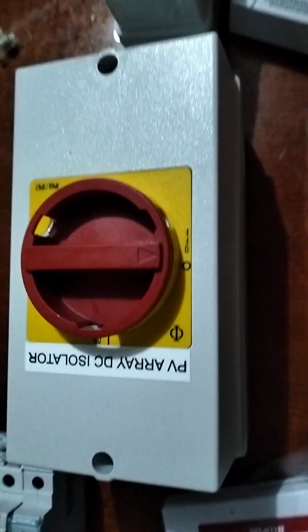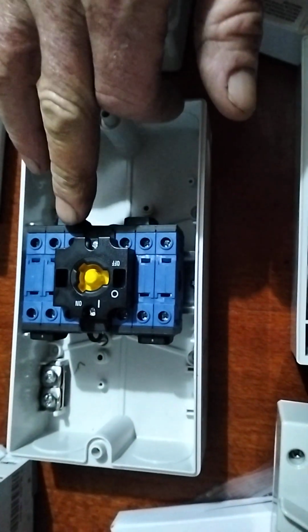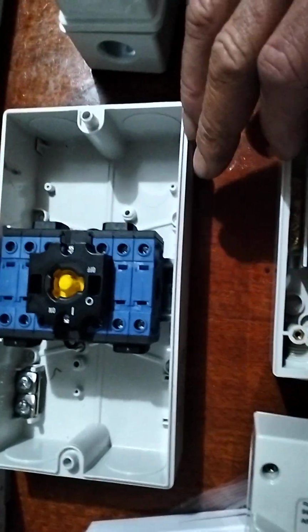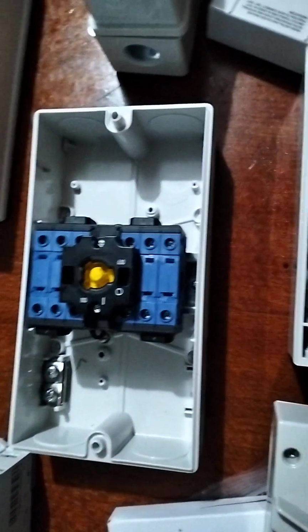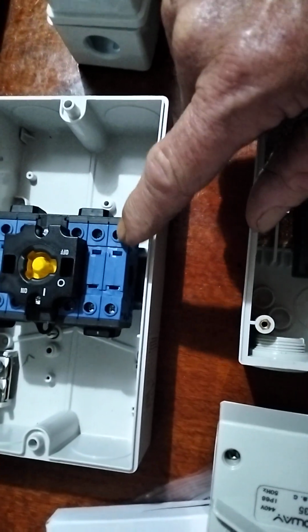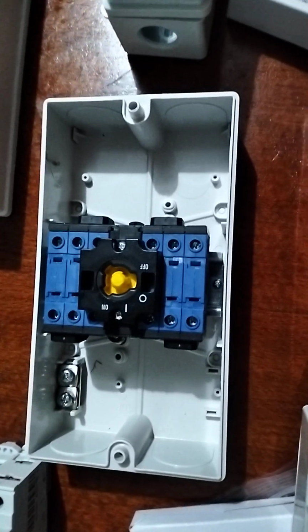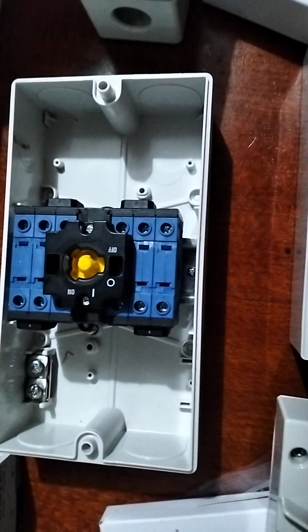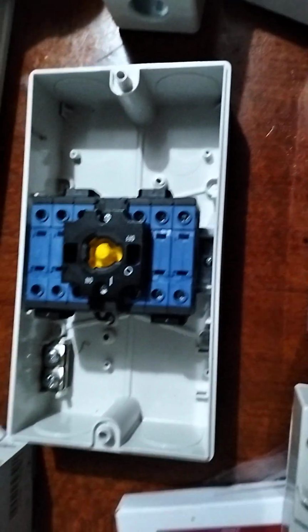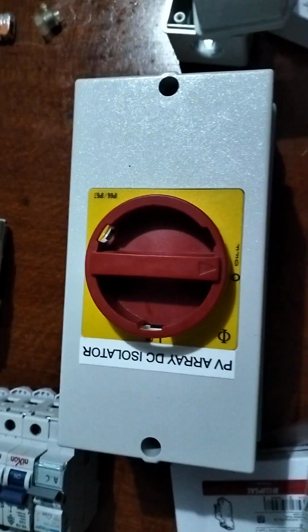Now your solar cell isolator, this is a PV array DC isolator. That's a special switch and I'll show you why. In here we've got 3 different poles on each side, so we've got a total of 6 poles, but one side is for the negative, one side's for the positive obviously. You can feed them in the top or the bottom, it doesn't matter. Obviously you've got an earth connector up there, but the point is they're 3 poles in series, so at the same time you've got 3 poles breaking the circuit in each of the legs, so you've got a total of 6 poles breaking the DC circuit. And that's extremely helpful. That should be used as your main PV array isolator.